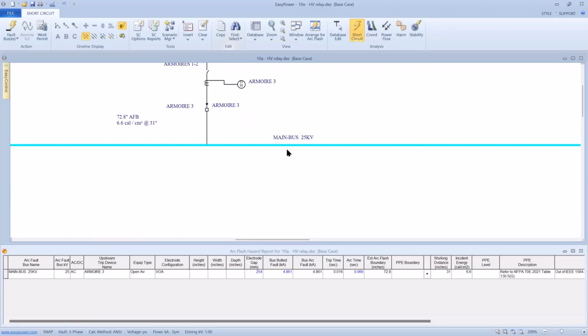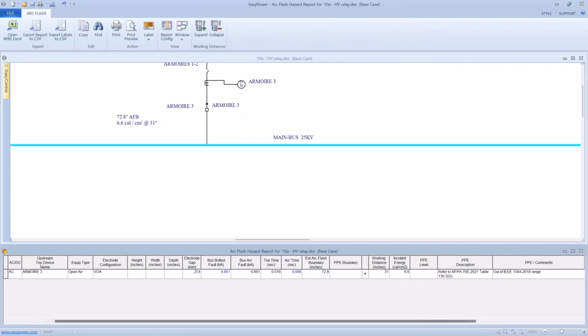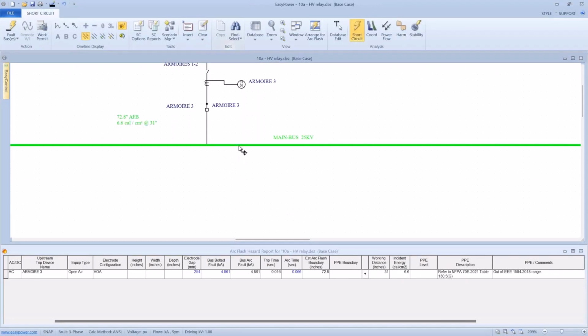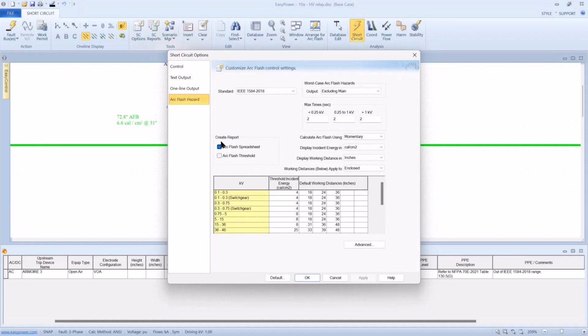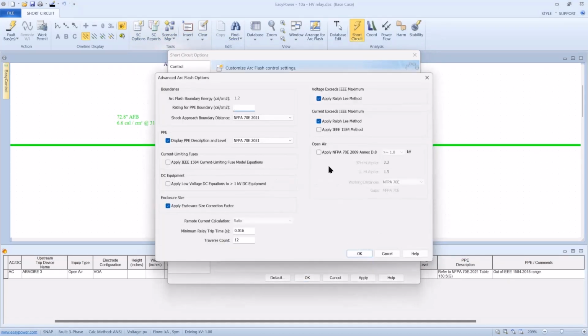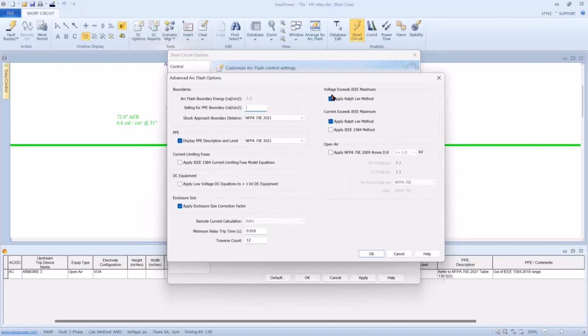But then I looked up and I said, well, this is a 25,000 volt bus, and it's open air. It's outside of the range of IEEE. So what's going on here? So let's go back to incident energy calculations, short circuit options, arc flash hazard tab, advanced. So the tool is automatically doing the Ralph Lee method rather than IEEE 1584. But the Ralph Lee method is for three-phase open air above 600 volts. And this is an open air bus.